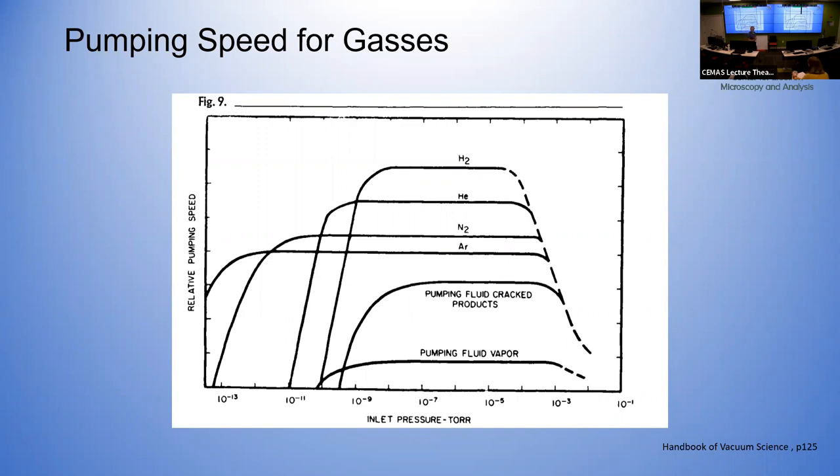So as the oil vapors come up, they are then directed downward through these vents in the chamber, and you get now a stream of heavy oil molecules hitting these very light gas molecules and imparting a net downward momentum to the gas molecules. Now, these are good through a certain pressure range, but if you start getting too many gas molecules, you lose the velocity of the oil molecules and they'll start to diffuse and go upward into your chamber that you want to keep nice and clean. So you do have to worry about oil back streaming from this type of pump, and they will usually put some sort of trap, both water cooled and liquid nitrogen cooled above a pump like this. So these big heavy oil molecules come out, they hit the gas molecules, push them downward, and then they condense with the water cooling on the wall, drip back down to the boiler at the bottom, and are recirculated. So these are generally very special oils with a very low vapor pressure that do not react well with oxygen, so they're very inert, and they're usually a silicone or a pentaphenyl ether type oil.